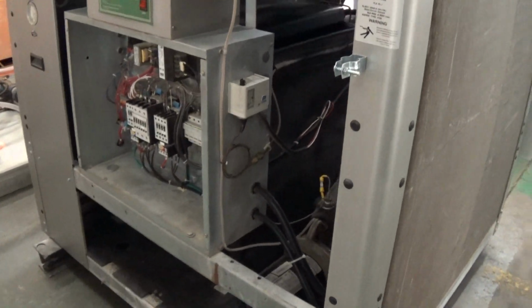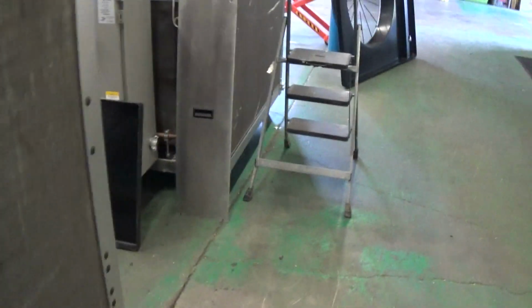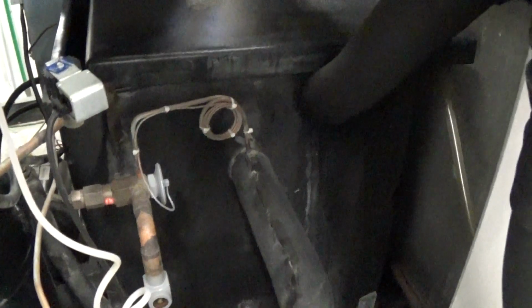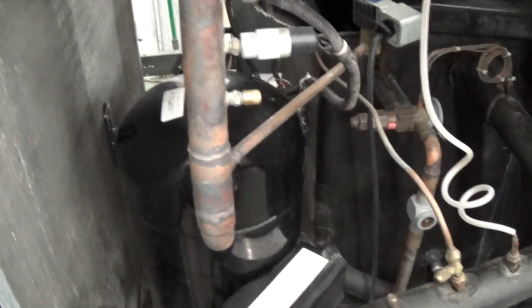This is a package chiller, meaning we have a pump and a tank in it. There's our reservoir tank there. On this design, the heat exchanger actually resides, you can't really see it, but you can see a bit of it. The heat exchanger actually resides in the tank itself. We have a 20 horsepower Copeland scroll compressor here. The unit has a 3 horsepower centrifugal pump. The pump here draws off the tank, then it discharges up and out to the process.